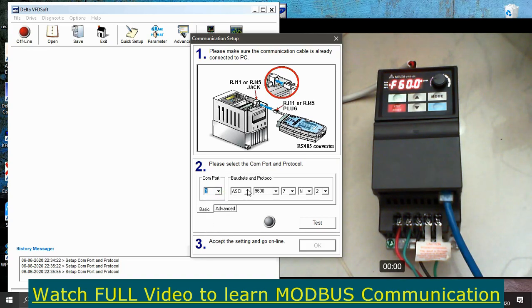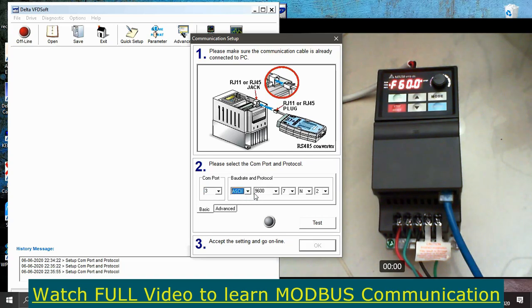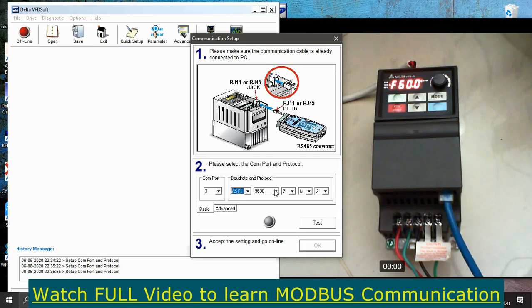Next are the baud rate and protocols. For protocols, I told you about ASCII mode and RTU mode — I'm going to use ASCII mode. Next is the baud rate, which is the number of bits transferred per second. I'm going to select 9600 baud, which is the manufacturer's default setting.